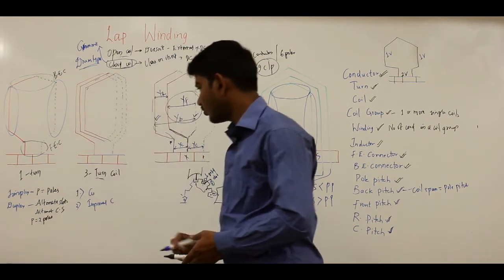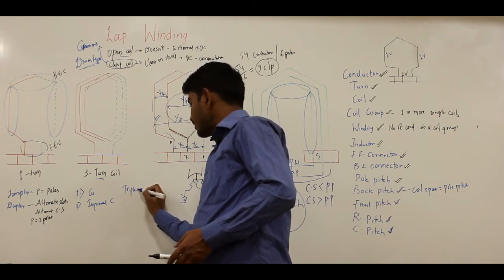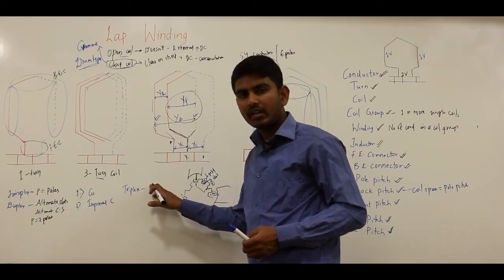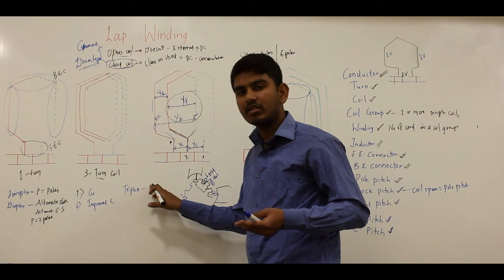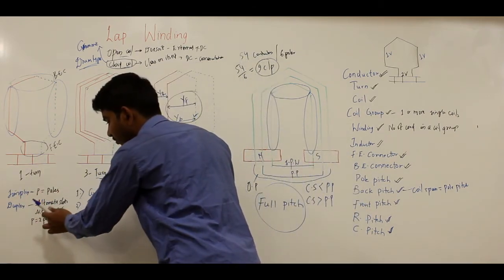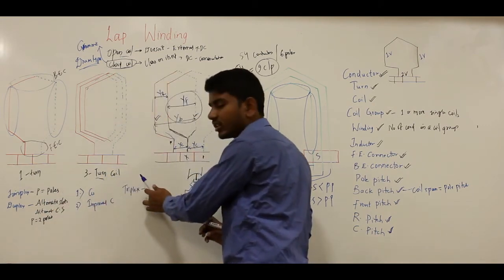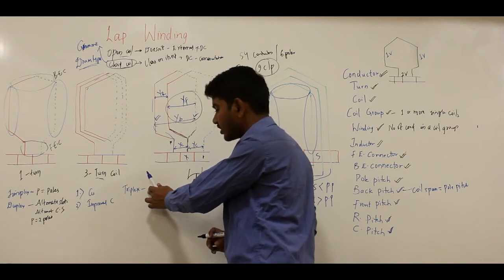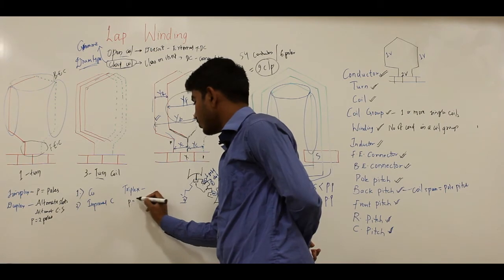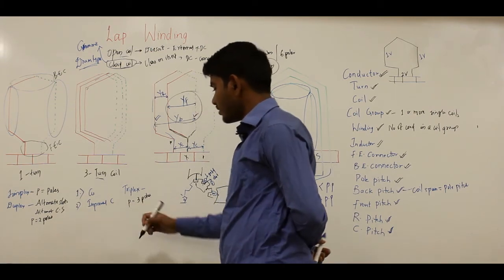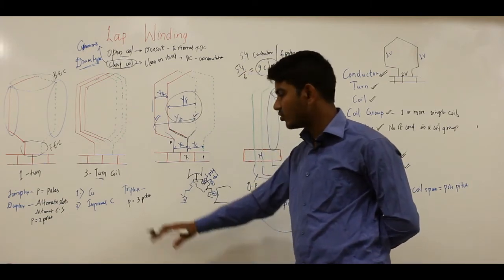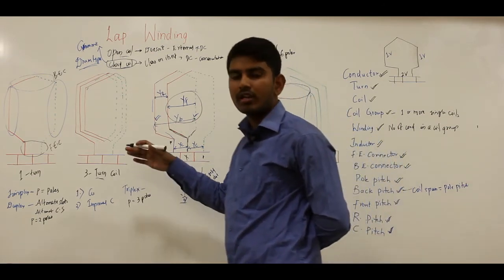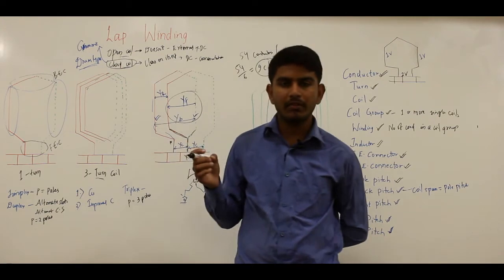In triplex winding, every third armature slot is occupied and connected to every third commutator segment, giving parallel paths equal to three times the number of poles. As more simplex windings are employed, the number of parallel paths keeps increasing. These windings can also be called multiple or parallel windings.